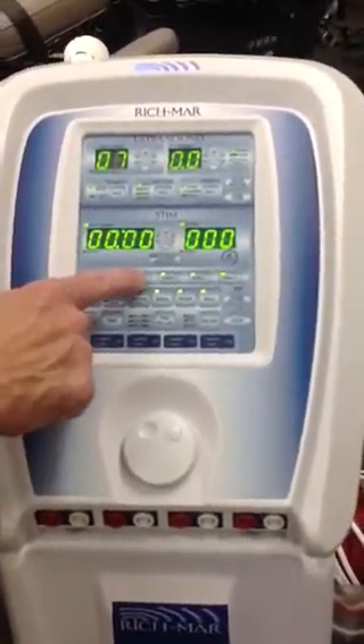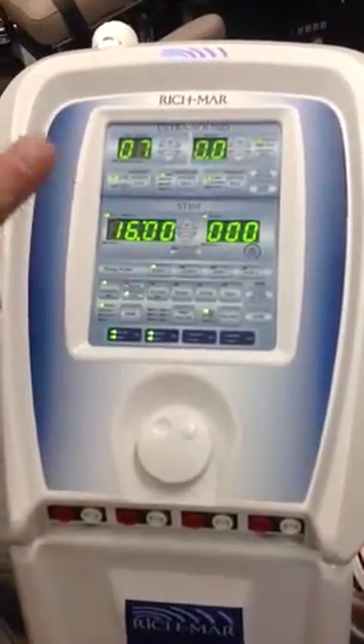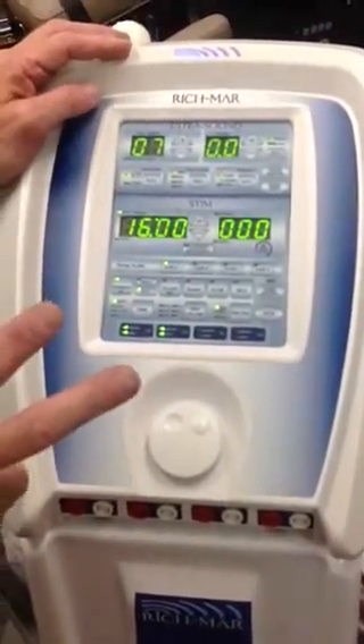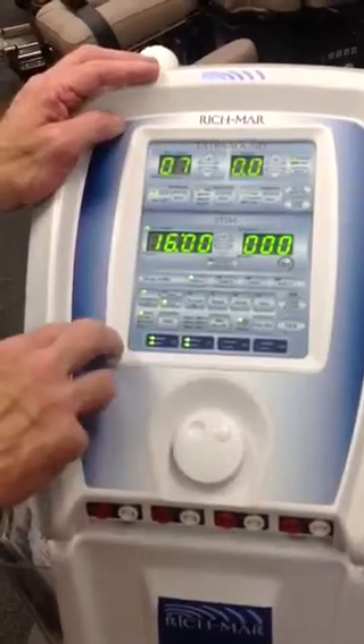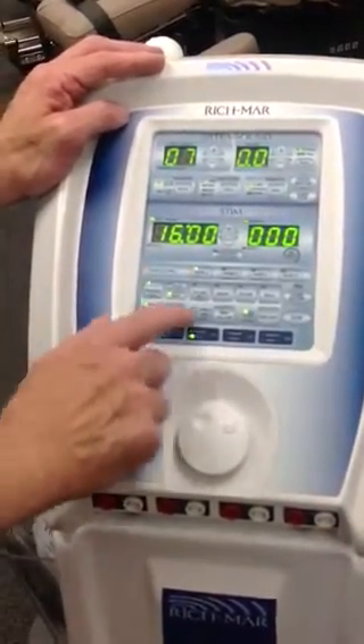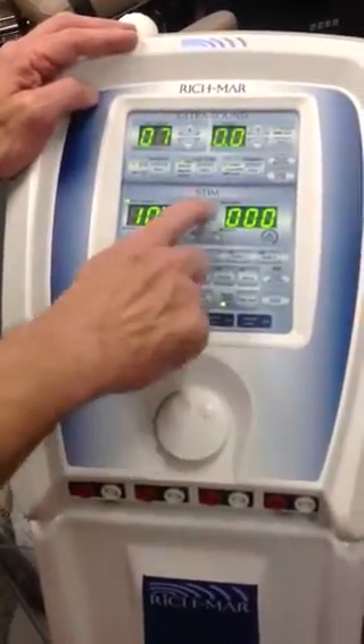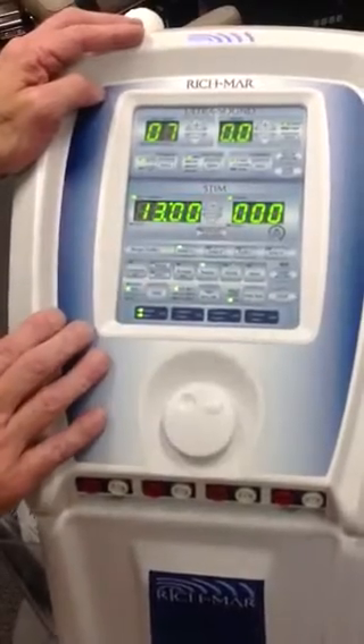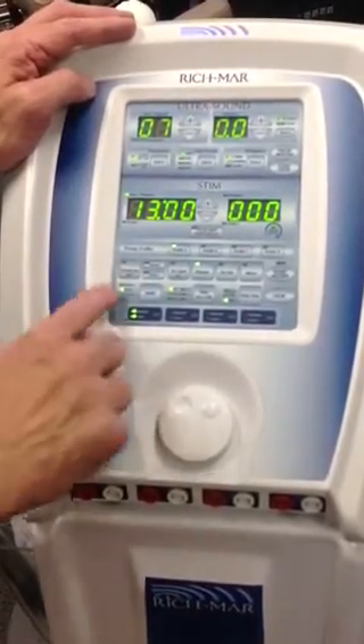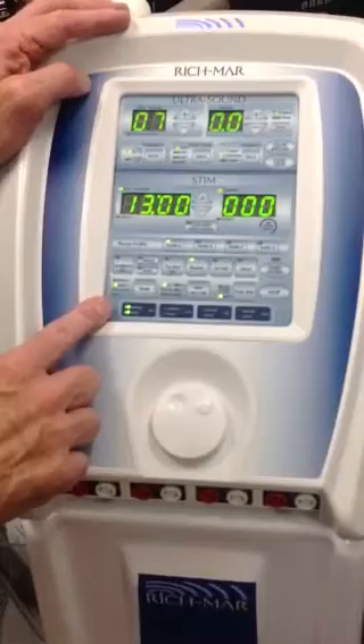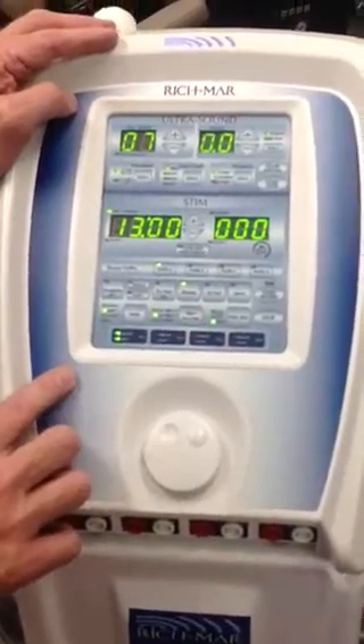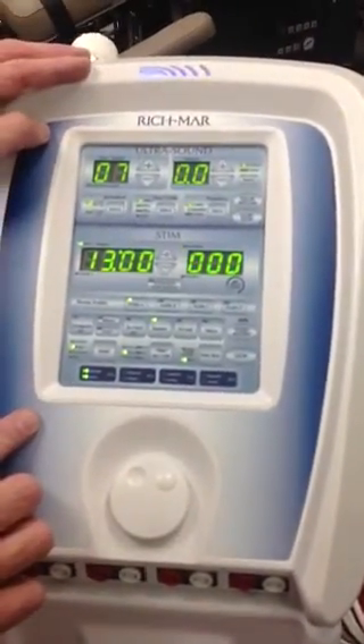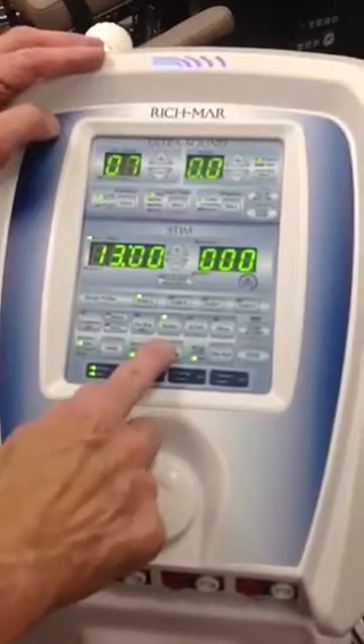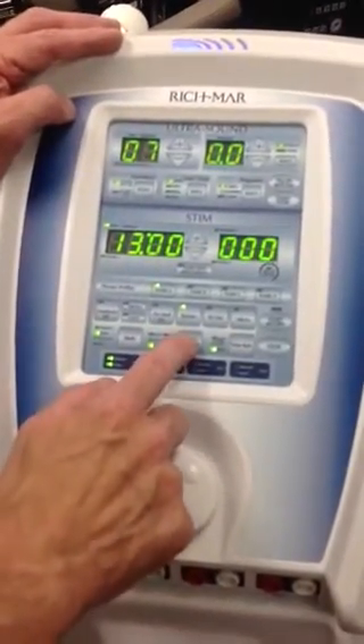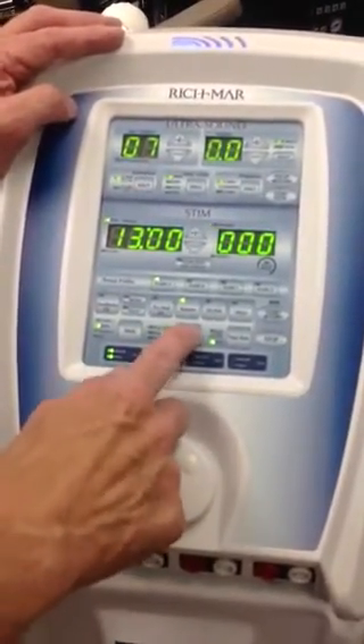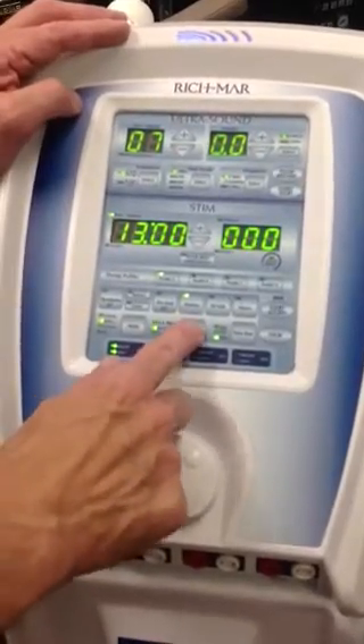In this example, we're going to press profile A twice. Once you press it twice, it's in program mode. So in profile A, I can make it Russian stim and make it 13 minutes. I can change any of the other parameters that I want. I can make it 10 seconds on and 30 seconds off, or 10 seconds on and 20 seconds off, or 10-10, or 10-5, or 5-5, whatever I like.